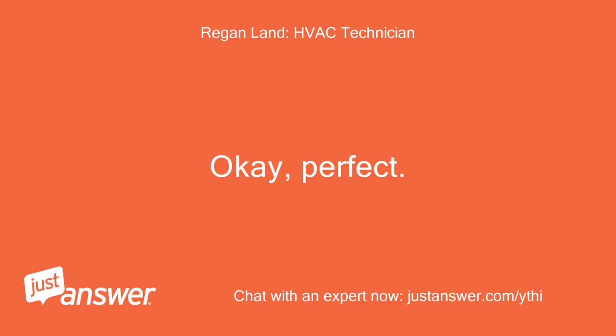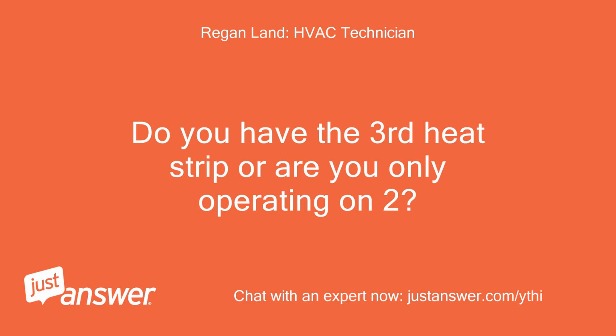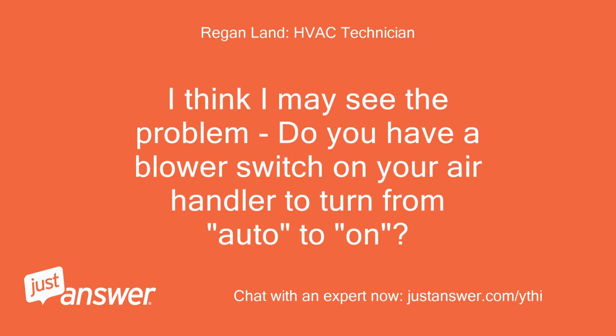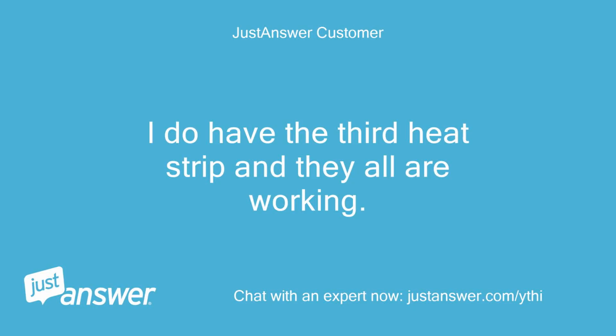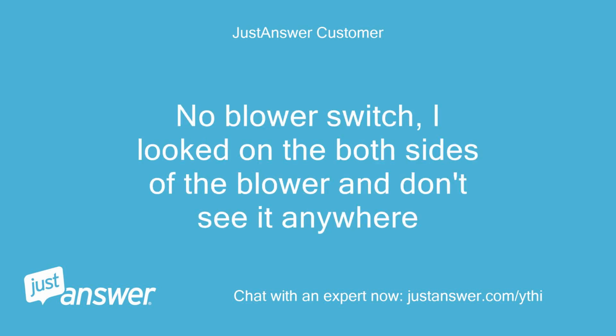Okay, perfect. Do you have the third heat strip or are you only operating on 2? I think I may see the problem. Do you have a blower switch on your air handler to turn from auto to on? I do have the third heat strip and they all are working. No blower switch. I looked on both sides of the blower and don't see it anywhere.